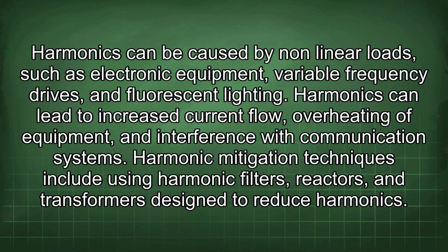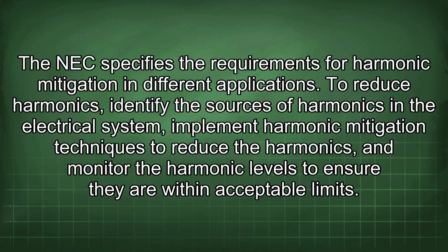Harmonic mitigation techniques include using harmonic filters, reactors, and transformers designed to reduce harmonics. The NEC specifies the requirements for harmonic mitigation in different applications. To reduce harmonics, identify the sources of harmonics in the electrical system, implement harmonic mitigation techniques to reduce the harmonics, and monitor the harmonic levels to ensure they are within acceptable limits.